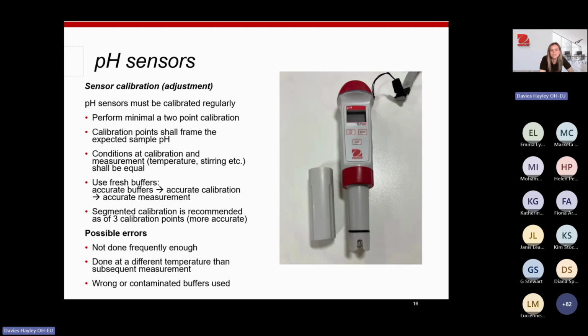The conditions at calibration and measurement should be equal. So you should always measure your sample and calibrate at the same temperature. Make sure your solutions are at the same temperature. What that means is, if you keep your calibration solution in the fridge, take it out of the fridge and bring it up to room temperature, the same temperature as your sample, just for accuracy. Always use fresh buffers, because accurate buffers equal accurate calibration, and that's accurate measurement. And if at all possible, 3-point calibration is always recommended, but a minimum of 2 points should be good.